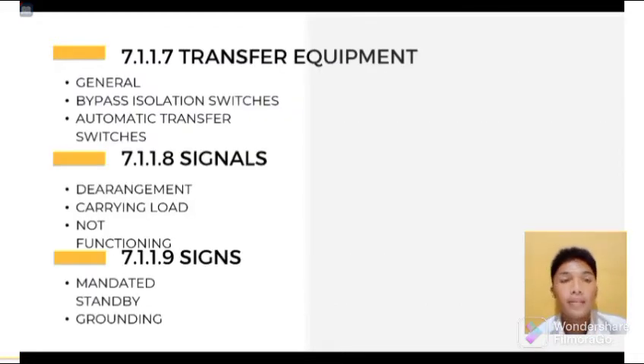Transfer equipment. Transfer equipment, including automatic transfer switches, shall be automatic, identified for standby use, and approved by the authority having jurisdiction. Bypass isolation switches. Means to bypass and isolate the transfer switch equipment shall be permitted. Where bypass isolation switches are used, inadvertent parallel operation shall be avoided. Inadvertent means hindi sinasadyang. Parallel operation shall be avoided.